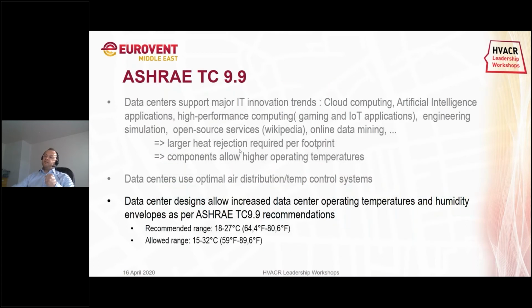Where is it leading to? As we mentioned, there are always major innovation trends, and we have already seen that data center operators were able to manage the air distribution. On top of that, they were using different temperature and control systems. All this allows the data center operating temperatures to increase, and this has been described in the ASHRAE TC9.9 recommendations. There you can see two different ranges, the recommended and the allowable. The recommended range provides device reliability and a long lifespan. The allowable range permits a wider tolerance while accepting some potential reliability risk for different reasons. It can be electrical discharge, or it can be temperature-induced failures. These are the ranges that data center operations have as a guideline to use these days.